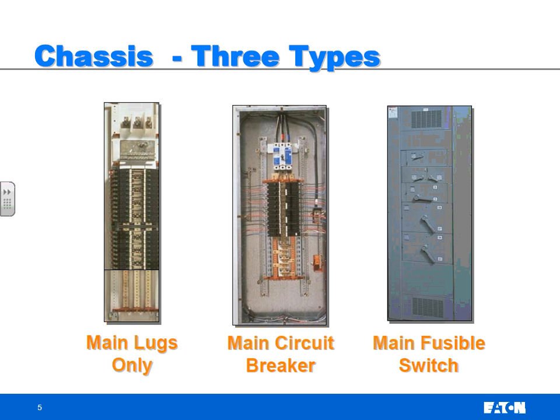Circuit breakers also, you can do a lot of things with circuit breakers that are tougher to do with fuses, like adding ground fault protection. Pretty easy in a circuit breaker. You can't necessarily do it with all fuses. You have to get a really big fuse to do it. Accessories, if you hear things on a circuit breaker like a shunt trip or an auxiliary switch, these are devices that you can actually mount inside of a circuit breaker. And you can open and close a circuit breaker remotely.